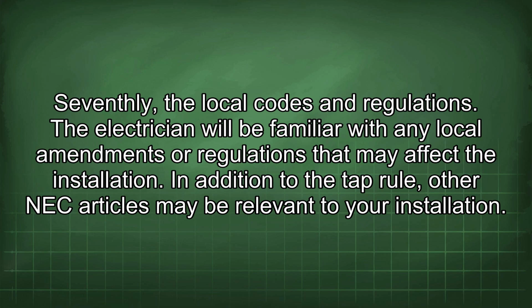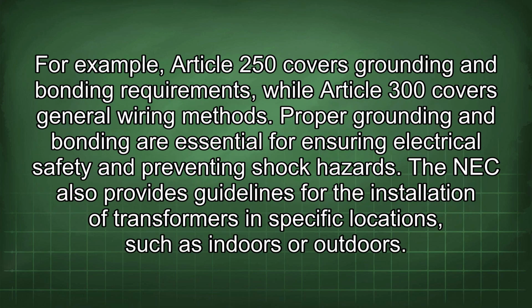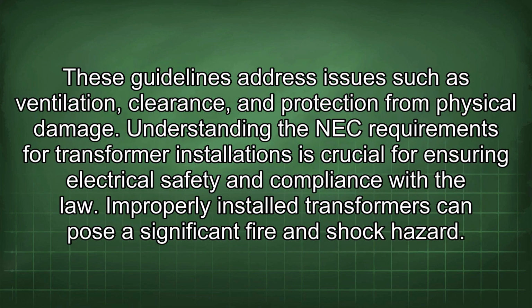In addition to the tap rule, other NEC articles may be relevant to your installation. For example, Article 250 covers grounding and bonding requirements, while Article 300 covers general wiring methods. Proper grounding and bonding are essential for ensuring electrical safety and preventing shock hazards. The NEC also provides guidelines for the installation of transformers in specific locations, such as indoors or outdoors. These guidelines address issues such as ventilation clearance and protection from physical damage.